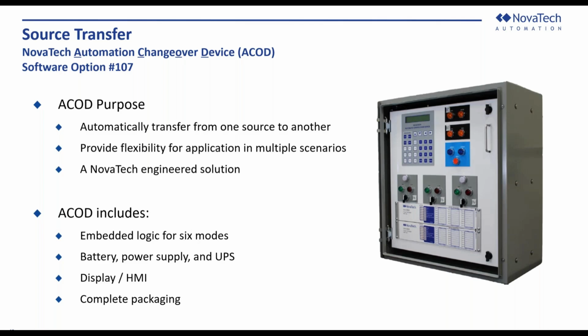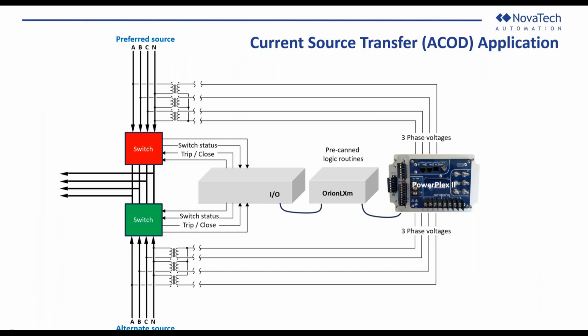Now let's take a look at how the current ACOD looks and how it works. In the current source transfer application, you can see there's a preferred source with a normally closed switch, and an alternate source with a normally open switch. It's exchanging inputs, outputs, and controls with an I/O, and that's feeding into the Orion LXM over comms. And then the PTs are being sensed with a PowerPlex meter. So the current design has 3 peripherals: I/O, LXM, and PowerPlex. We're trying to enhance this and use fewer devices and do the same, if not better.